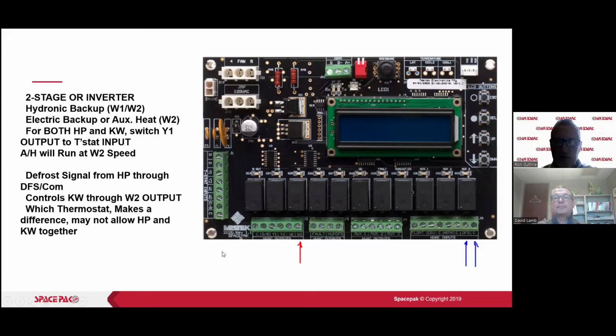Okay, so go on. What we're seeing is the defrost controller requires 24 volts to power it. Yes. Okay. So this DFS here is where the W, typically it's W on a heat pump, coming back up to here. But we don't typically have the common coming back from our heat pump. What we need to do here is grab a common off of our thermostat, or off of this connection. So we just need to grab a common from someplace else. That's all.